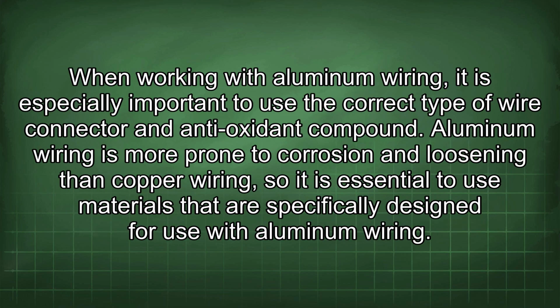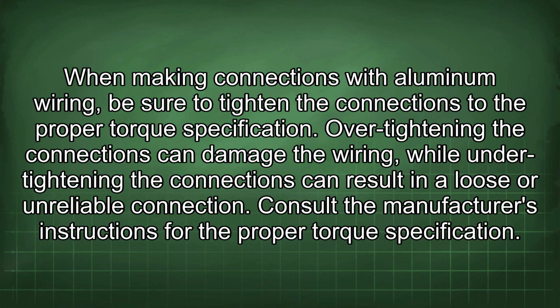When working with aluminum wiring, it is especially important to use the correct type of wire connector and antioxidant compound. Aluminum wiring is more prone to corrosion and loosening than copper wiring, so it is essential to use materials that are specifically designed for use with aluminum wiring. When making connections with aluminum wiring, be sure to tighten the connections to the proper torque specification. Over-tightening the connections can damage the wiring, while under-tightening the connections can result in a loose or unreliable connection. Consult the manufacturer's instructions for the proper torque specification.